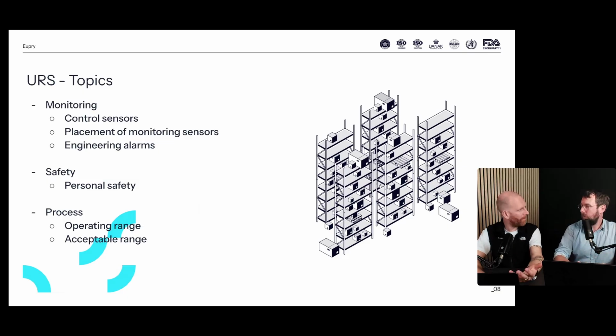Generally, when we talk ambience, we say 15 to 25. So when you say operational range 10 to 30, that's 5 below and 5 above. Yes, something like that. It's just often we see equipment being spec'd only for where it's expected to be used. But having an operational range, which you would of course afterwards verify or qualify, just gives you that flexibility up front. And that's also one of the key points we'll bring in later in the slides, that over-restricting yourself just because that is what you need today can sometimes backfire.